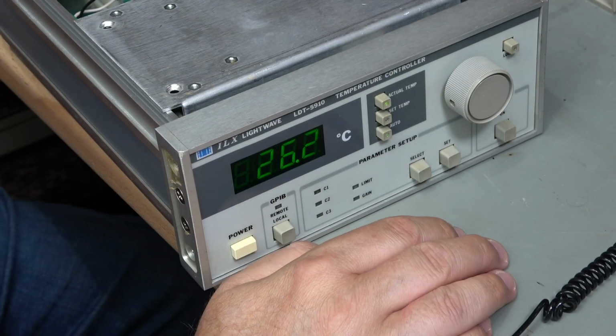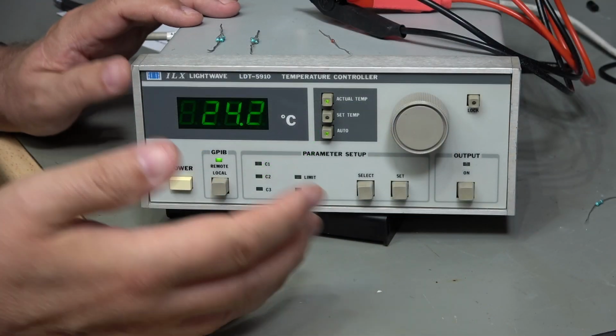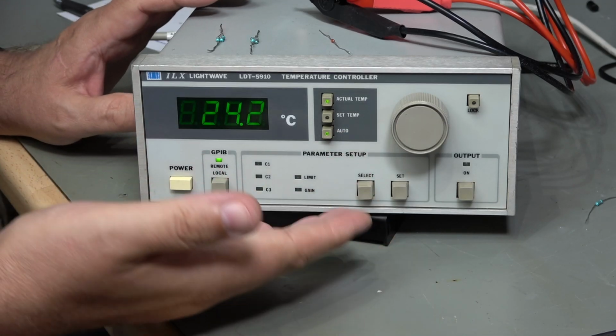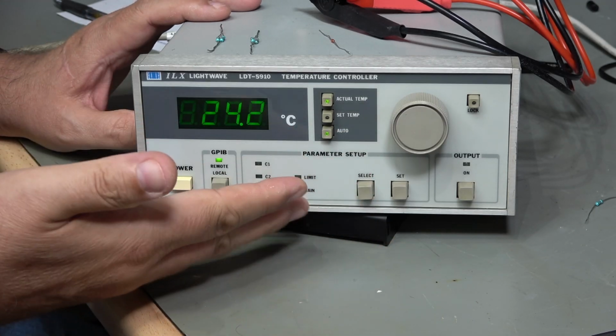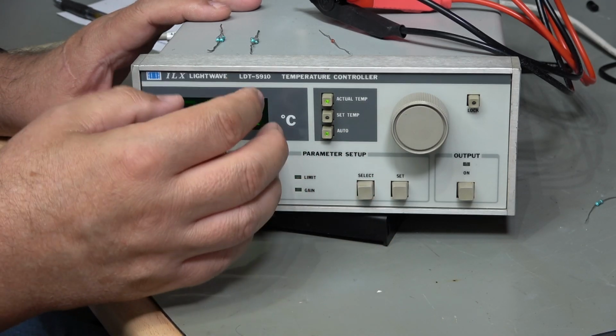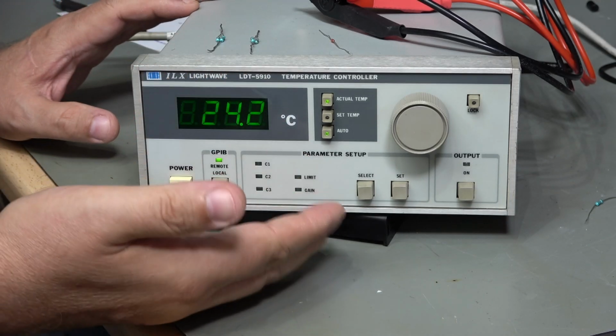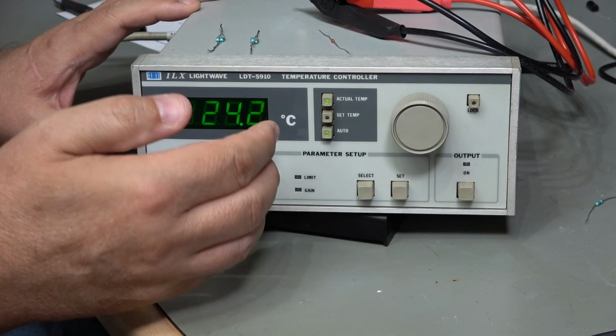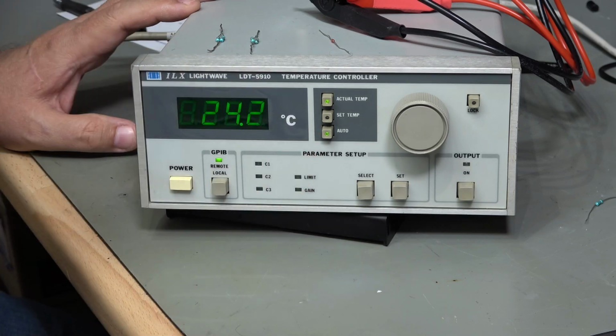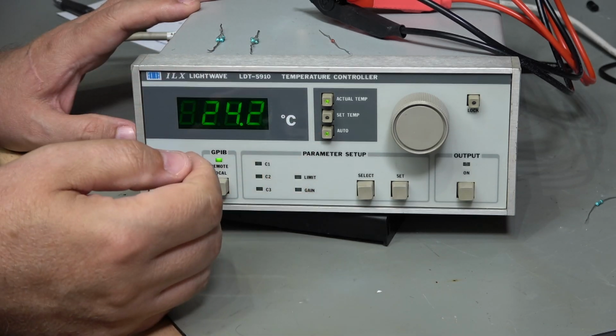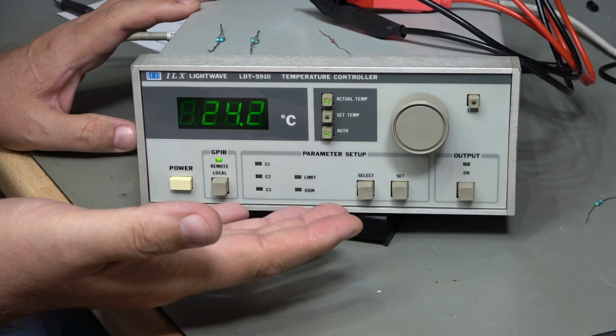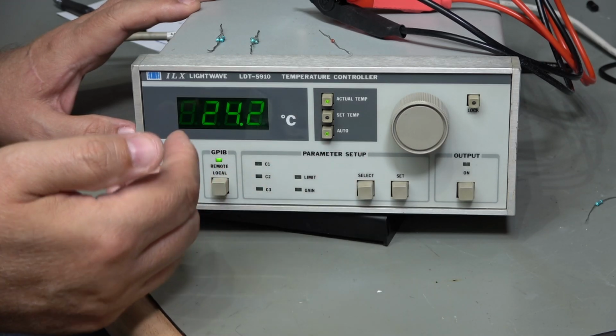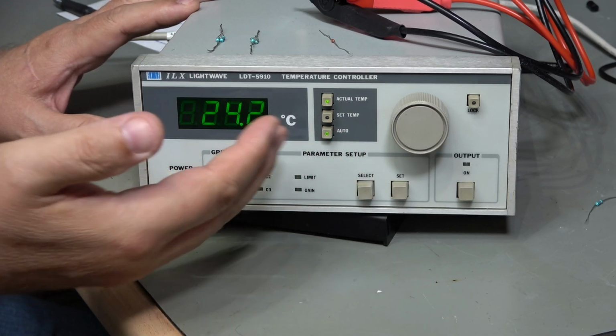Right, let's get this reassembled and then I can actually recalibrate. So I'm ready to calibrate this. There are two types of calibration. The first is for the unit itself, and that's so it can read resistances very accurately, because if it can't do that, then it's never going to be able to work out the temperature. And as we saw in the circuit diagram, there are relatively low tolerance resistors involved, 5% resistor for example on the output, and only 1% resistors on the current control circuit. So the op amps involved as well have input voltage offsets. We want to calibrate all of that out if we can.